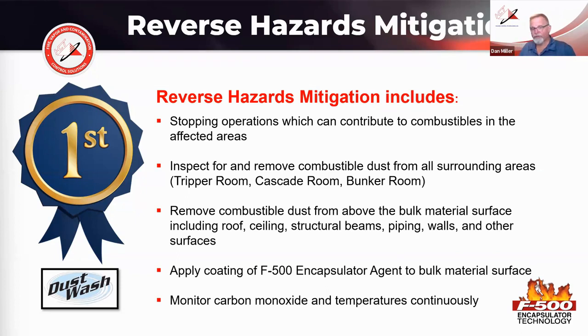If you use plain water and just start spraying it around indiscriminately, you can actually cause an explosion. So you have to be very careful about how you go about removing that dust, but it does need to be done prior to attacking the acute problem. So we get rid of that secondary explosion capability. And then we apply a coating of F500 to the bulk material surface itself or the acute problem area, as we continue to monitor for carbon monoxide and monitor temperatures with thermal imagers throughout. And it's a teamwork based process.